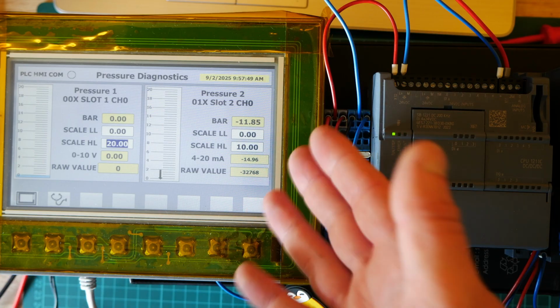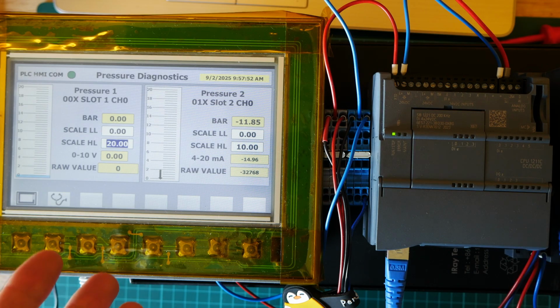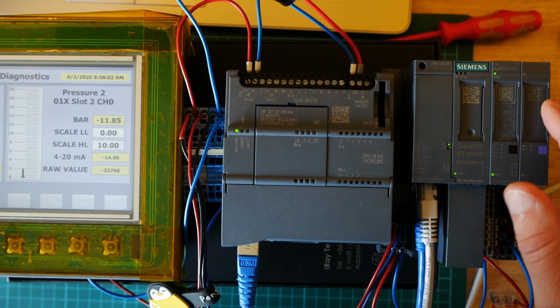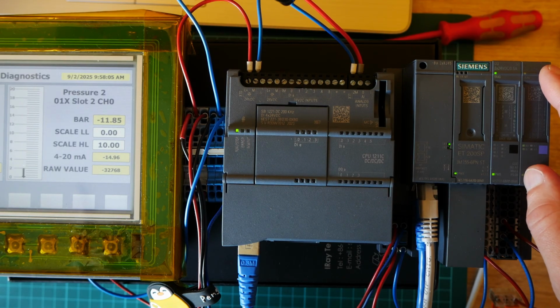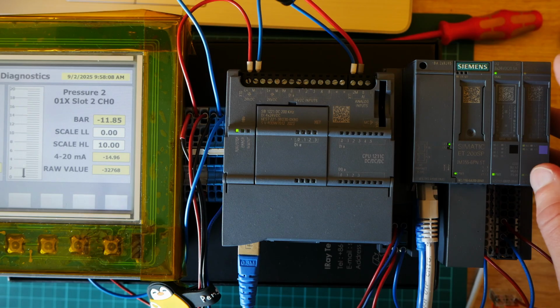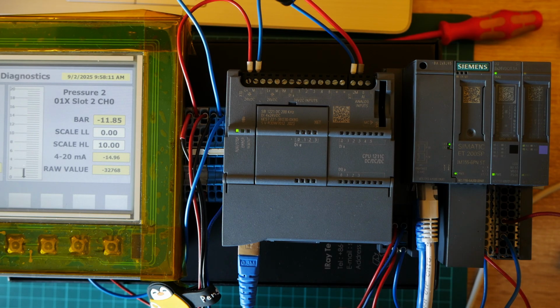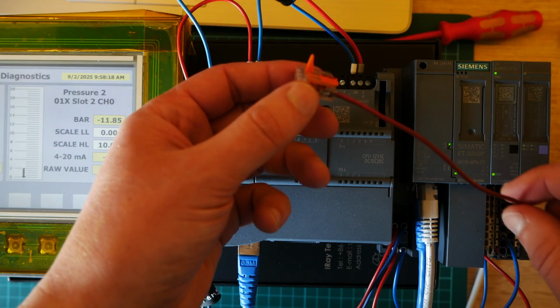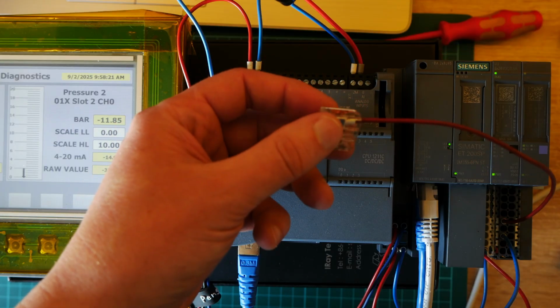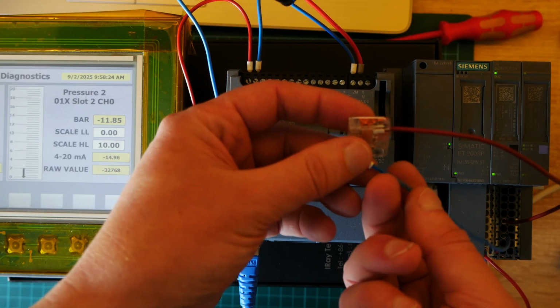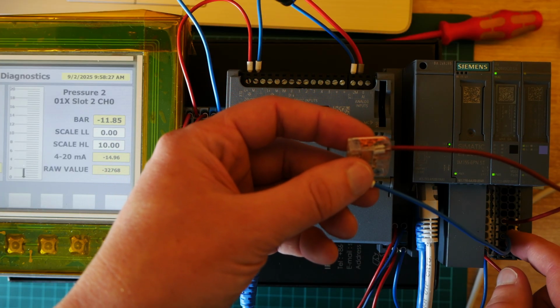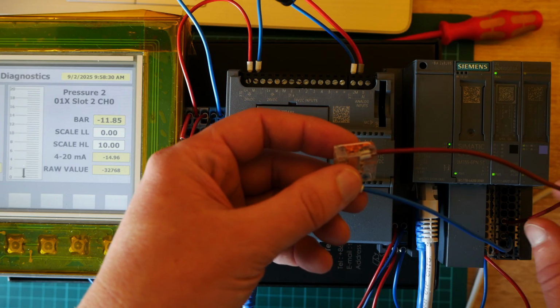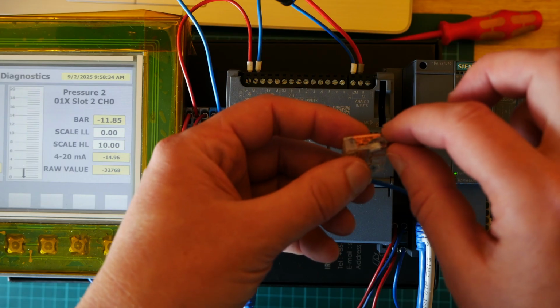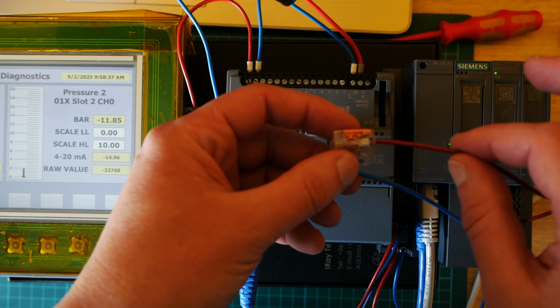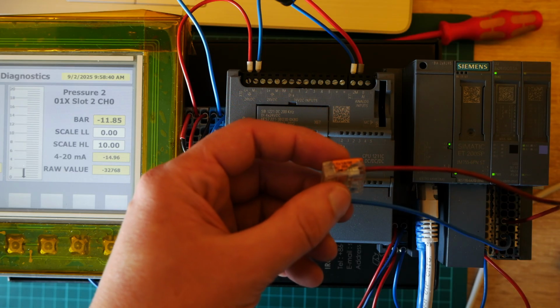As I said, this video is about when we don't have a process calibrator. So how do we test whether this analog card is working or not? How does this two-wire analog input card work? You basically have two wires. One wire provides voltage to your sensor, to your transducer, and this value comes back to your analog input card. So here we have 23.5 volts. It's not going to be 24 volts, it's going to be something less.